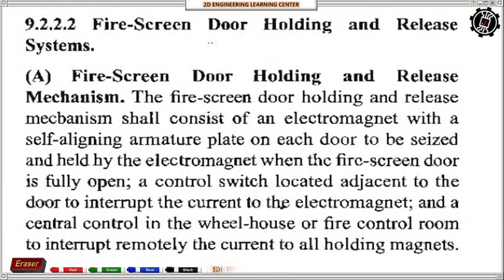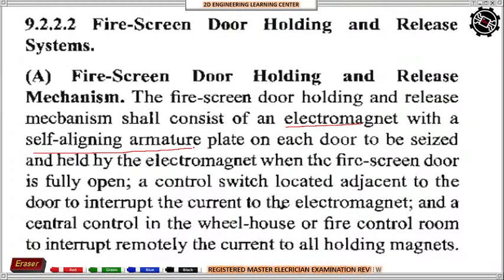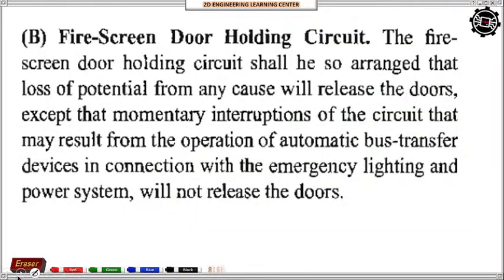Okay, so fire screen door holding and release system. The fire screen door holding and release mechanism shall consist of an electromagnet with a self-aligning armature plate. When there is a fire, it will automatically close the compartment where the fire is, and then the sprinkler system will work.